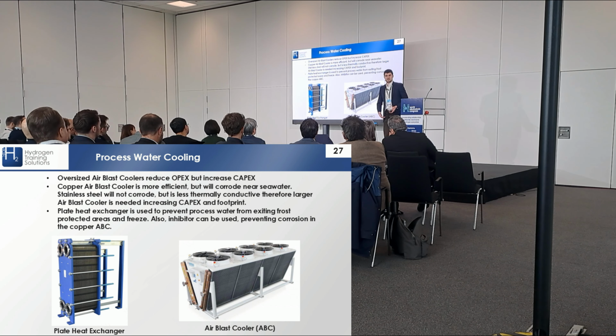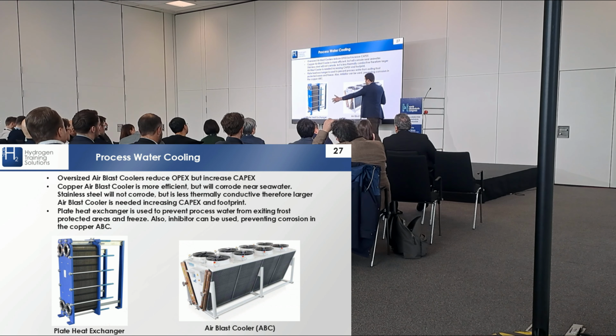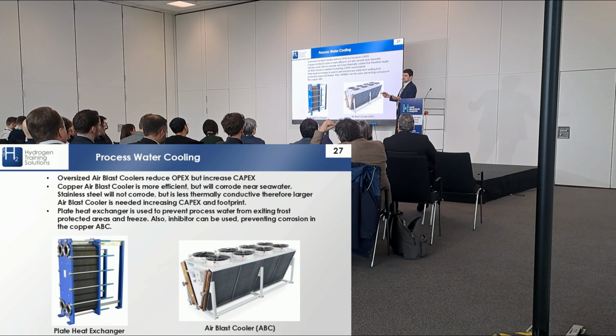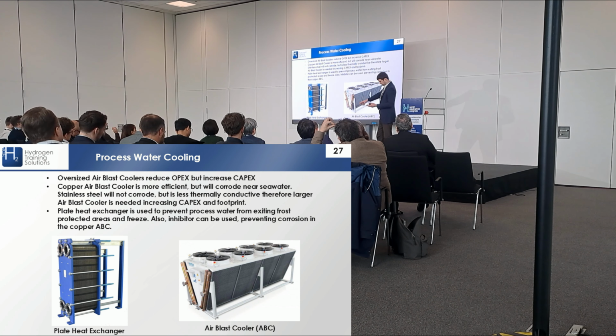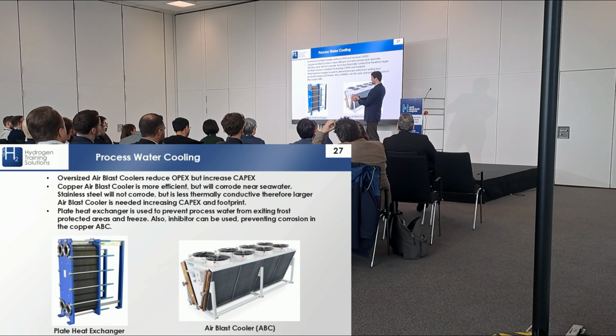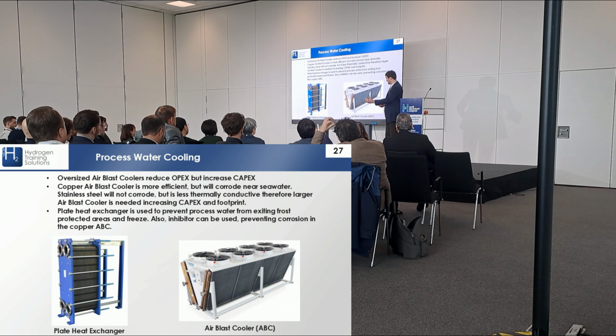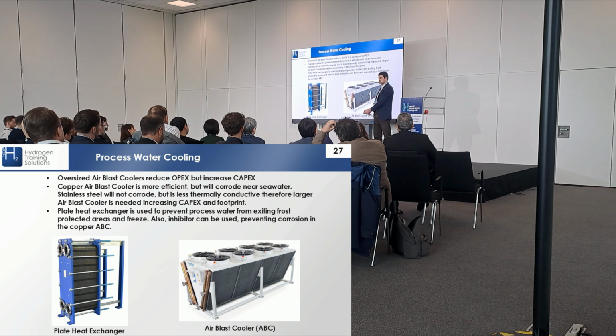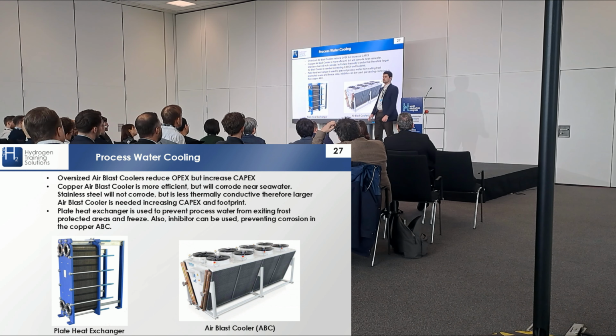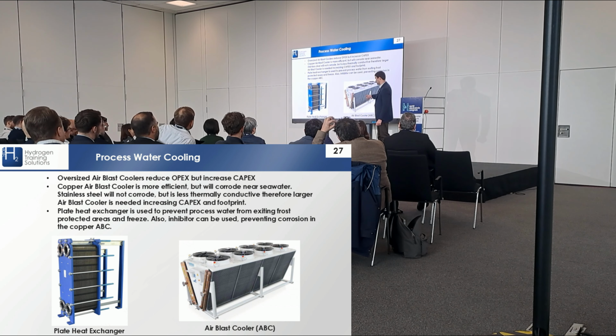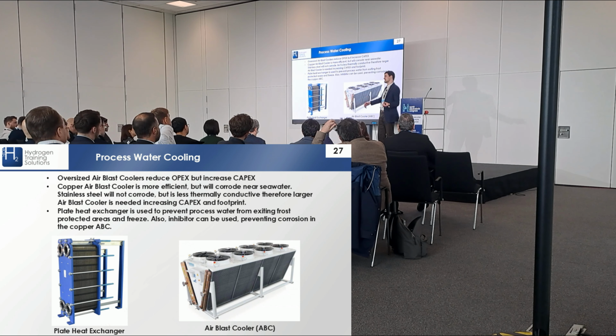And the trouble with stainless steel is that it's not as efficient at conducting heat, so you are going to need a larger air blast cooler, and of course that is going to mean an increase in capex and an increase in footprint. And the second reason that you need the plate heat exchanger, so the first one was freezing, is that if we were to pass process water through the air blast cooler, we could not use copper, or we could, but that would be terrible for the stack long term, and it would also corrode, because we cannot use an inhibitor. We would have to use stainless steel for the air blast cooler, which means it would have to be larger, again, bigger footprint, bigger capex.